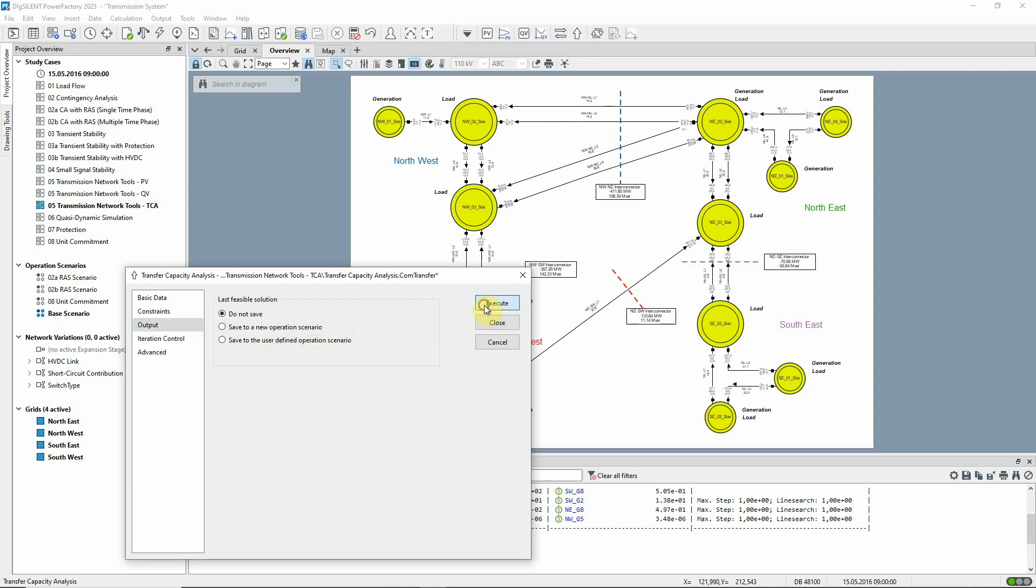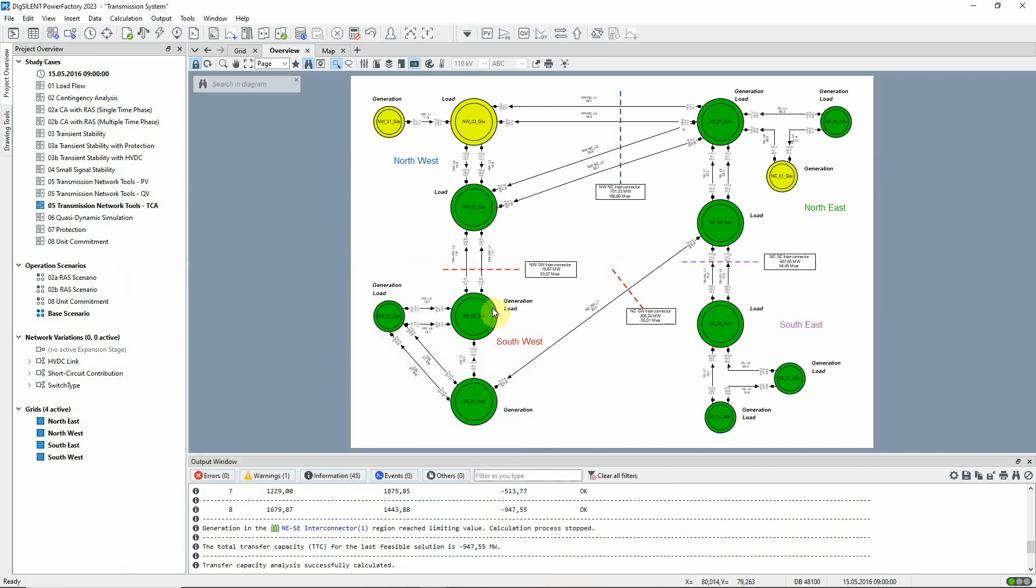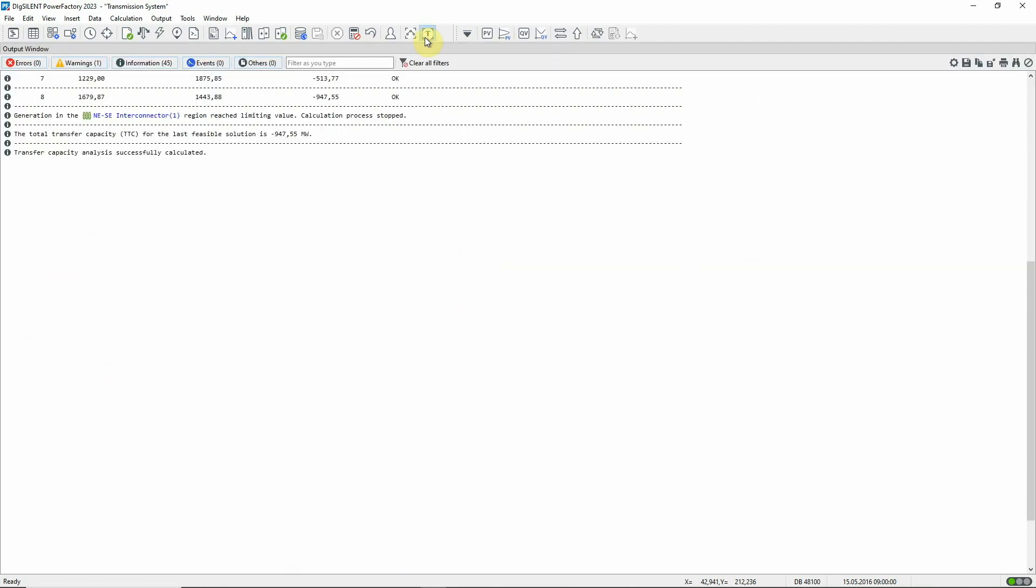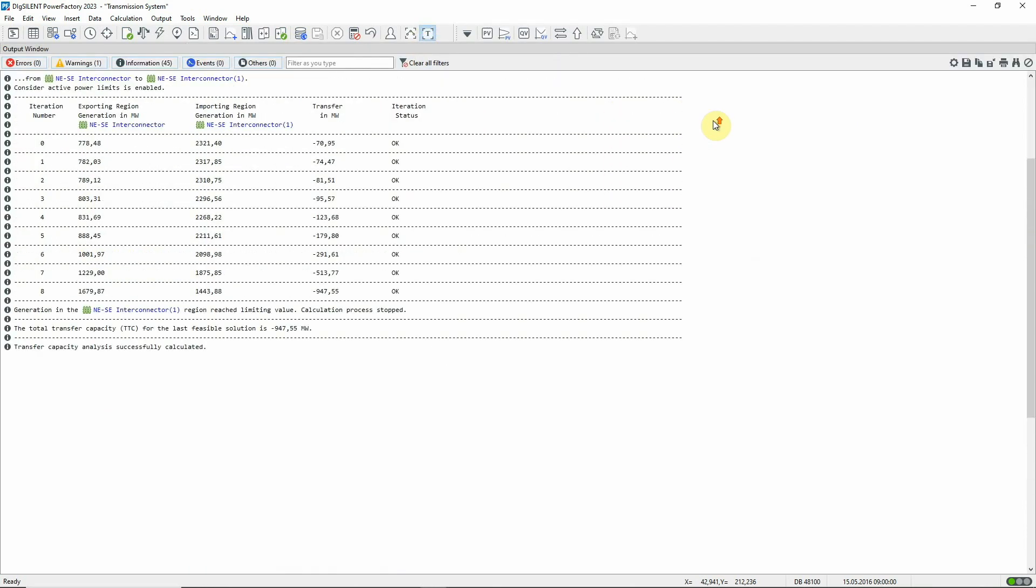The analysis is executed and we can see in the output window that the total transfer from the southeast to the rest of the network has a limit of about 948 megawatts.